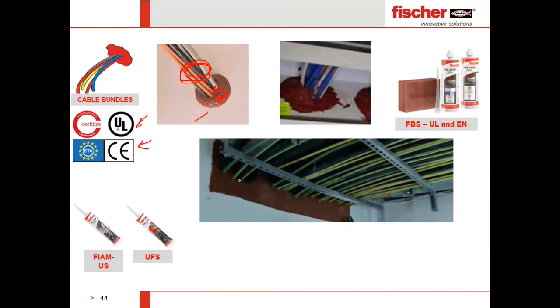Sometimes, when we have a lot of cables like this, we need to put material which is easily expandable and easily removable for maintenance, especially for networking cables. So we have this type of brick where you can fix the bricks, and when fire happens, this will melt together and close the gap. And if there is no fire and we need to remove it for maintenance, we can easily remove and maintain the gaps.